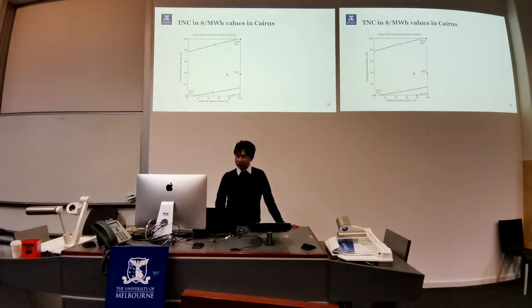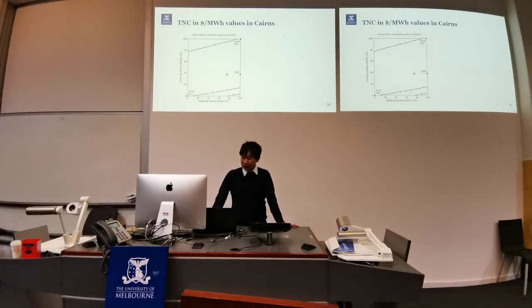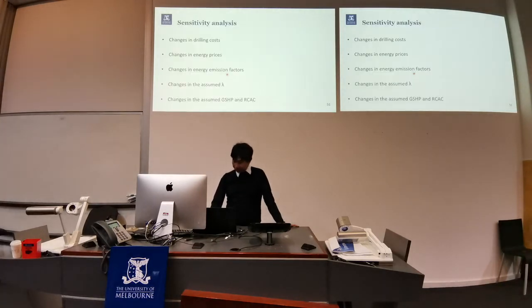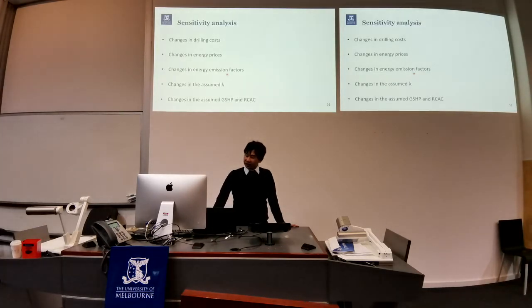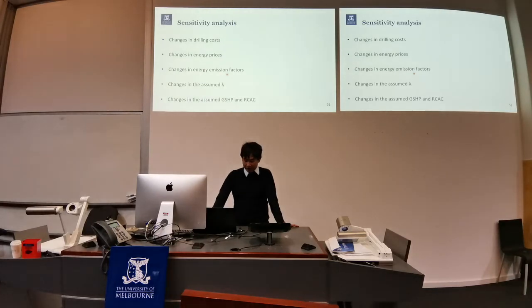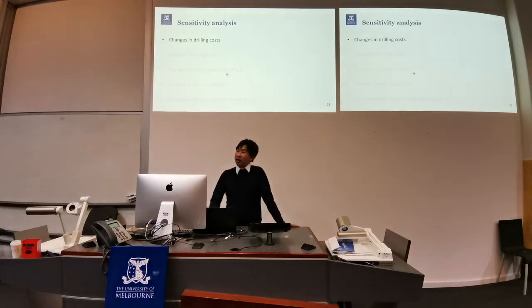In this case, the lowest normalized cost is $148 per megawatt hour, where the heat pump is designed to meet about 38% of the peak load. This hybrid combination reduces the ground heat exchanger length requirement by almost half compared to a full ground source heat pump system. The next step is to conduct sensitivity analysis of some key parameters. Changes in any of these parameters can severely impact the financial feasibility of the system. For this presentation, I will just show the first one, which is changes in the drilling cost.